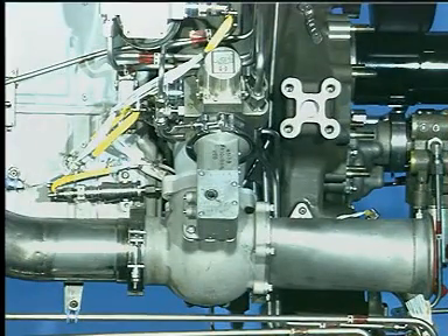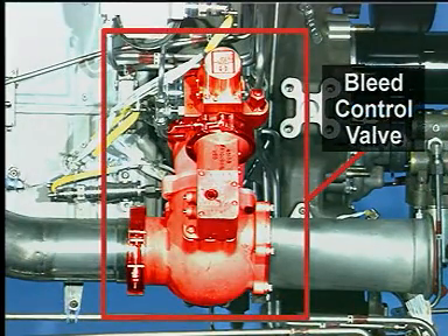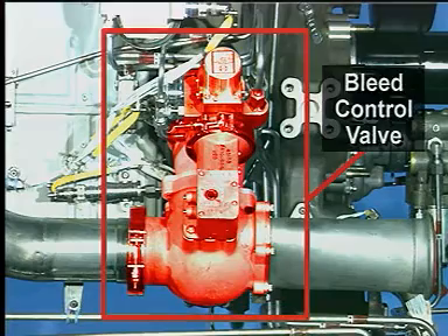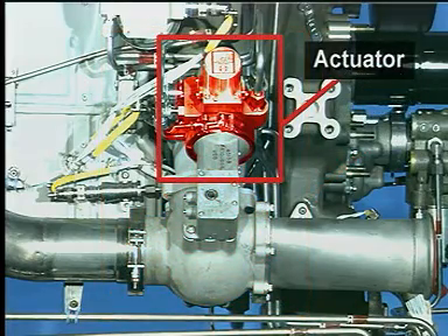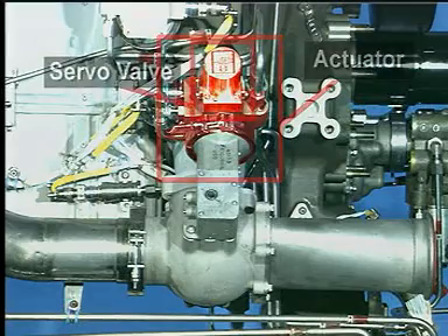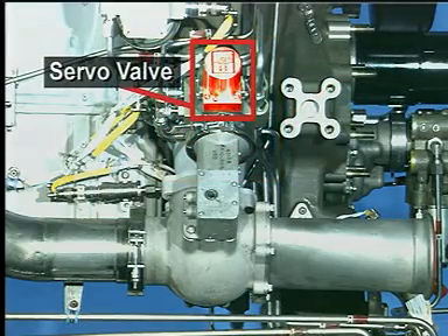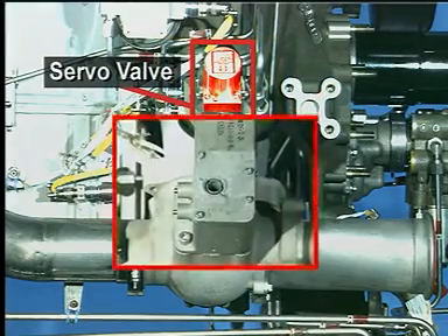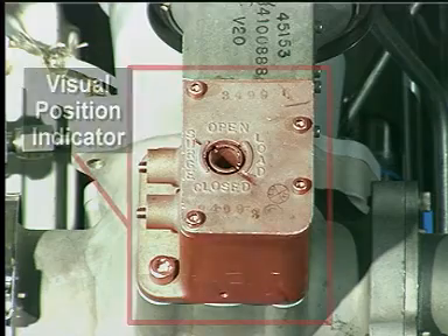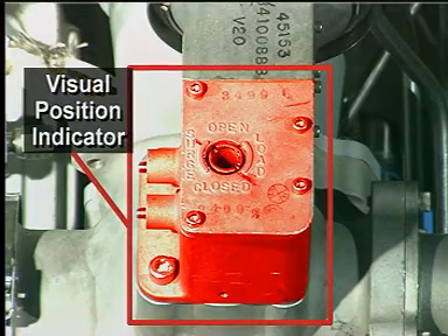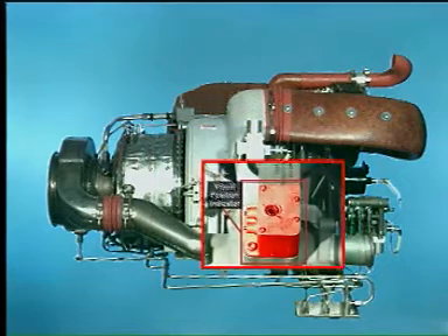The air supply from the load compressor is controlled by the bleed control valve. The butterfly type valve is installed on the compressor outlet scroll at the 3 o'clock position. It is operated by a fuel servo actuator. The servo fuel is supplied from the fuel control unit pressure regulator and controlled by a servo valve. The bleed valve position is indicated by a visual position indicator and monitored by an internal linear transducer.